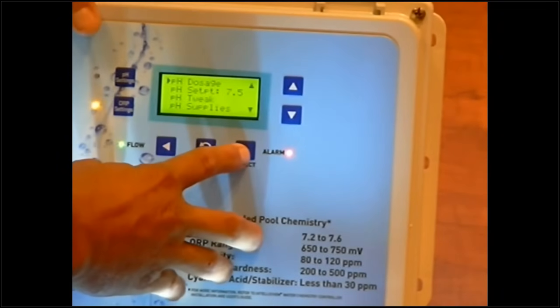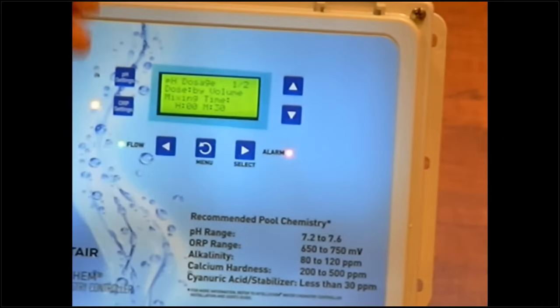So we'll go ahead and press select on this dosage, and this is the mixing time. Basically, what this mixing time does is I like to set this for 30 minutes. It comes set up at an hour. So every 30 minutes, it's going to be adjusting the pH and mixing the water for 30 minutes before it readjusts and retests. It's gonna test the pH and adjust it. You can do it more frequently or less frequently. I recommend once we set this for you, I'd probably leave it right at that level, but there are adjustments to be made if you need to.